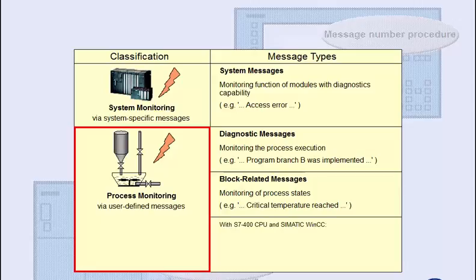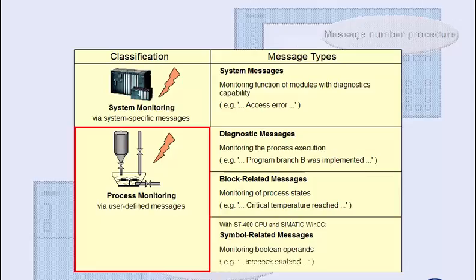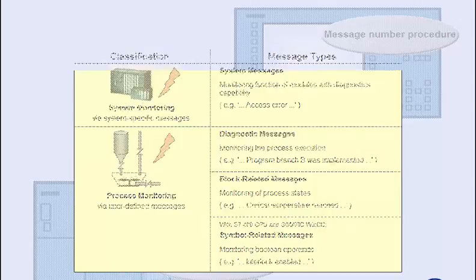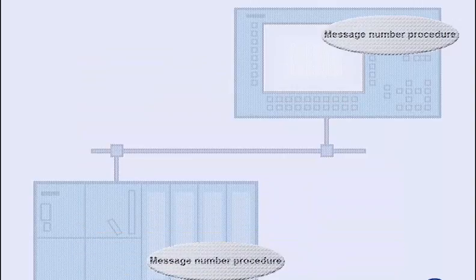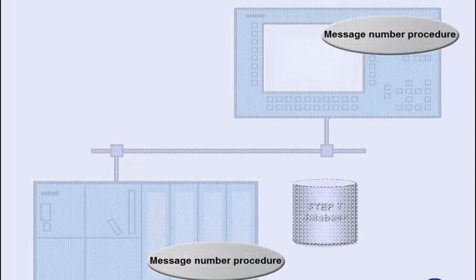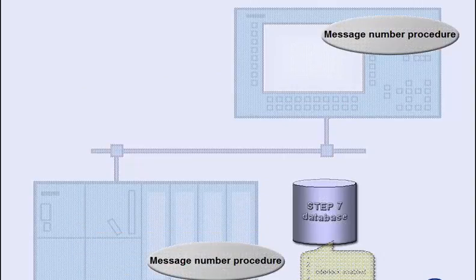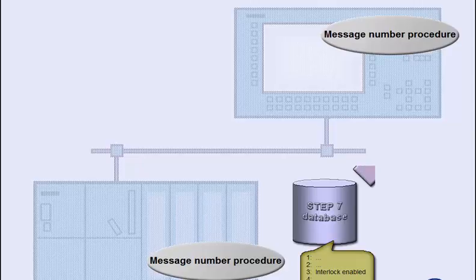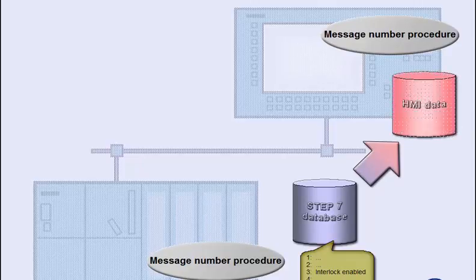With an S7-400 CPU and SIMATIC WinCC as HMI system, it is also possible to configure symbol-related messages for monitoring Boolean operands directly in the symbol editor. All these message types basically work on the same principle. When the messages are configured in Step 7, the texts and attributes are stored in the common database, and passed on to the operating device during the transfer of the HMI-relevant data.